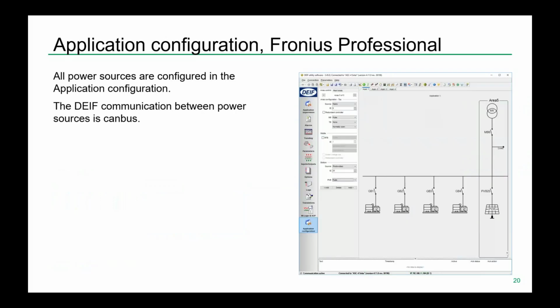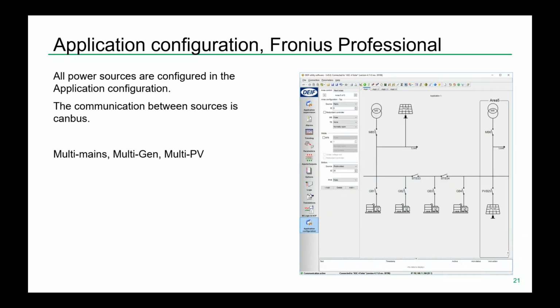On the professional solution, it's a little bit different. In the new applications, it's a fully integrated solution. All controllers communicate with each other. So this means they can see each other, basically. And everything is drawn in the same application configuration. So in some way, it is easier. And here I just want to show that you can actually, in a flexible way, configure your application. I just show 2 utility incomers, 2 points of connection for the solar, the same 4 generators, but now separated with bus tie breakers or bus couplers. So it's just to show that you have several possibilities to create your application.